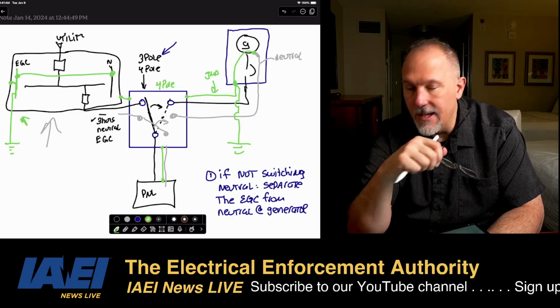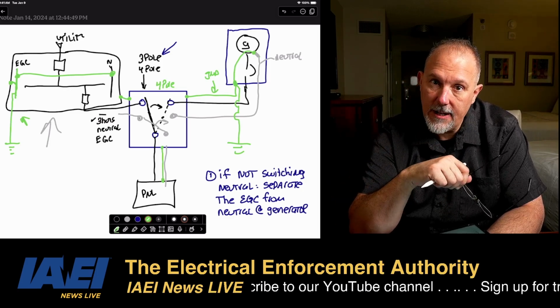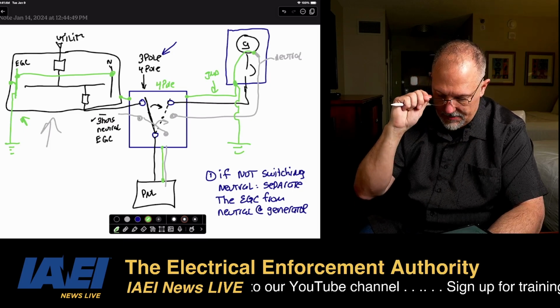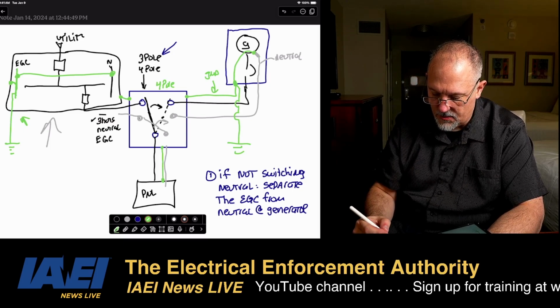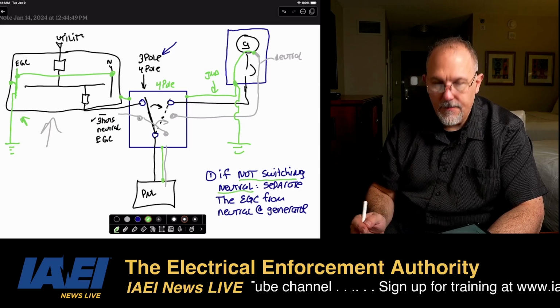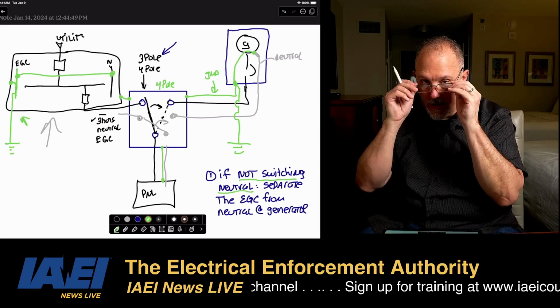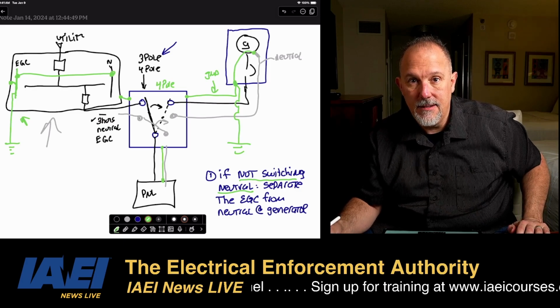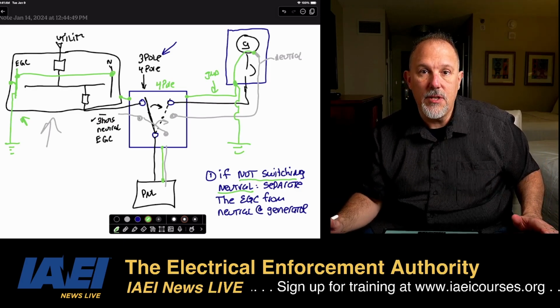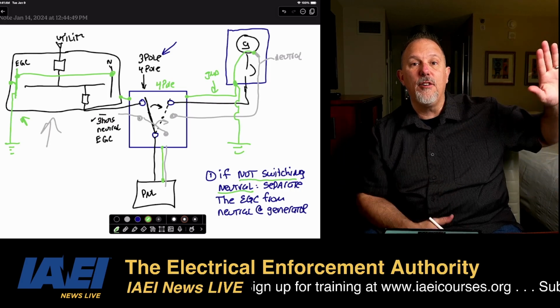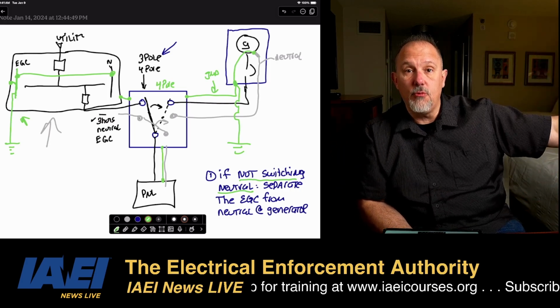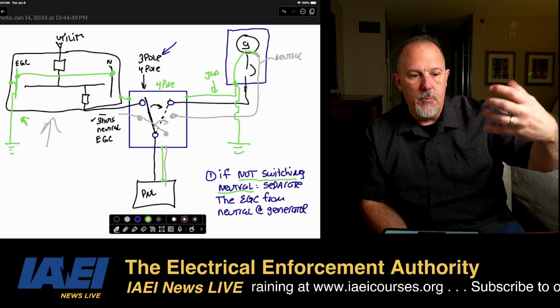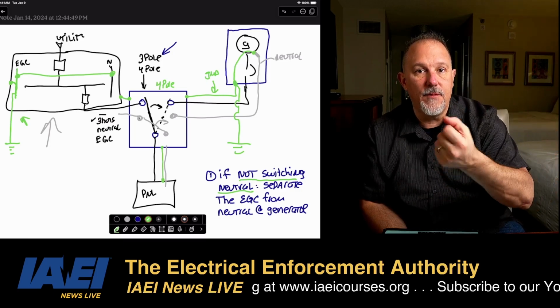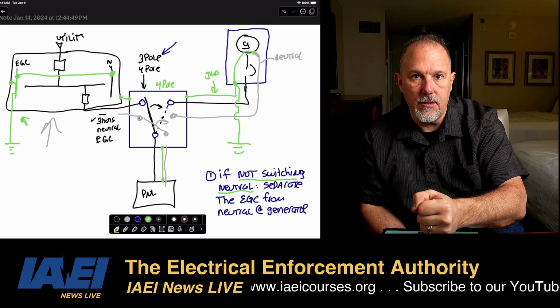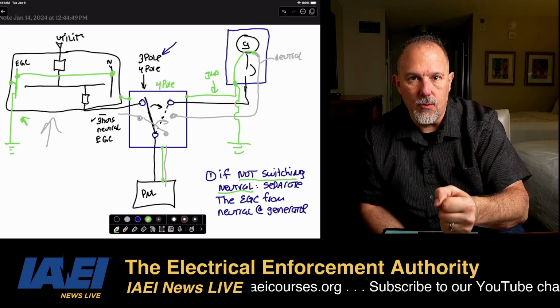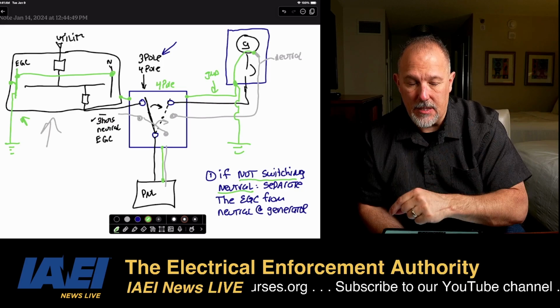If it's single phase, it would be a 3-pole instead of a 2-pole, right? That's why I just said I eliminated the poles. I said not switching the neutral. If you're not switching the neutral, then that generator is not separately derived, because the neutral is common between both systems, and you're relying on the grounding in your service equipment for that bond and ground for the system, for that grounded conductor. If you're switching the neutral, then the generator is a separately derived system.